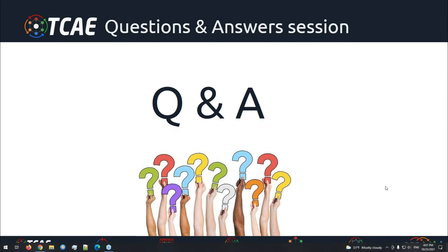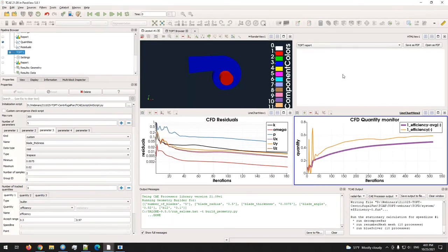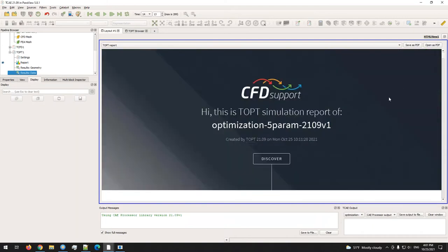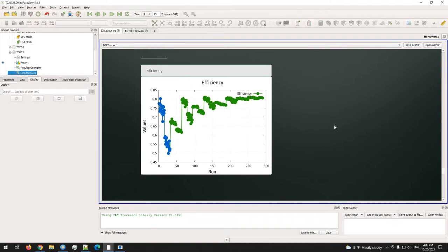Okay, so this is not relevant. What's the efficiency? Ilya Pankratov is asking, what's the efficiency of your examples? I think it's visible, right? The formula for efficiency is in the manual. The value of efficiency, if that is the question, is about 80%, which is the top of centrifugal fans. They can go like 80 to 83. That's the best results possible of the best fans of our clients we know. And of course this case is artificial, so it's based on a real project, a real existing fan, but it's artificial. But 82 is a very good value for a centrifugal fan of this size.